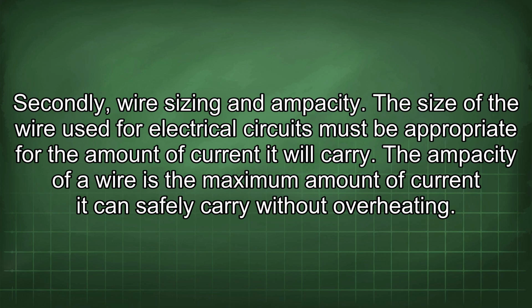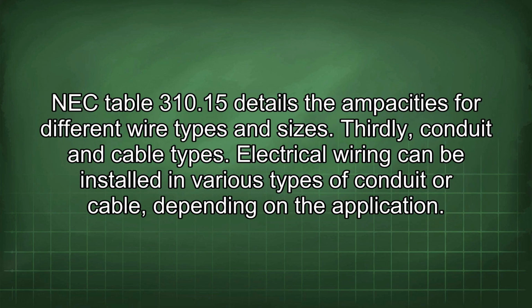The size of the wire used for electrical circuits must be appropriate for the amount of current it will carry. The ampacity of a wire is the maximum amount of current it can safely carry without overheating. NEC Table 310.15 details the ampacities for different wire types and sizes.